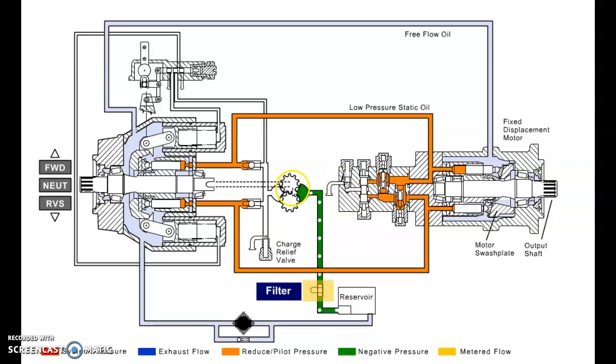We've also got our charge pump here in the center and a filter on the suction side, which tells me this is an industrial unit, not mobile hydraulics where we'd be outside in cold weather because you don't want to pump through a filter on the suction side of a pump for mobile systems.